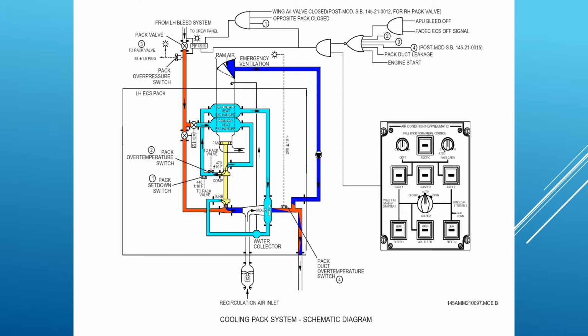There are two protection switches now, overtemp switches. There's the pack overtemp switch and the pack set down switch. We'll talk about the overtemp first. That's set to 243 degrees C, and if the temperature leaving the compressor gets to 243 degrees C, it will cause the pack to shut down, and once it's shut down it's latched. The crew would have to reset it on the switch. The set down switch, I'll talk about that in a minute.